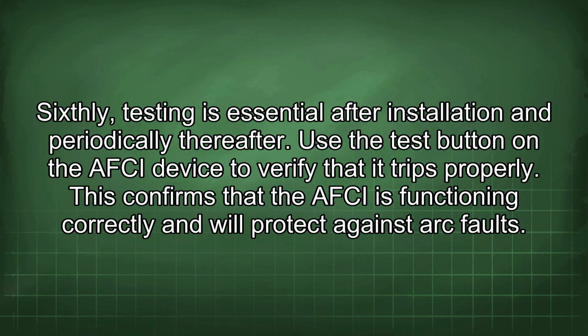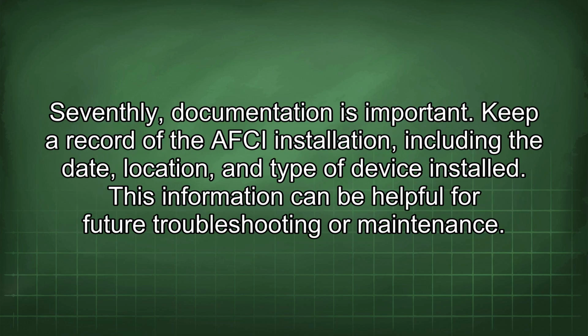Sixthly, testing is essential after installation and periodically thereafter. Use the test button on the AFCI device to verify that it trips properly. This confirms that the AFCI is functioning correctly and will protect against arc faults. Seventhly, documentation is important. Keep a record of the AFCI installation, including the date, location, and type of device installed. This information can be helpful for future troubleshooting or maintenance.